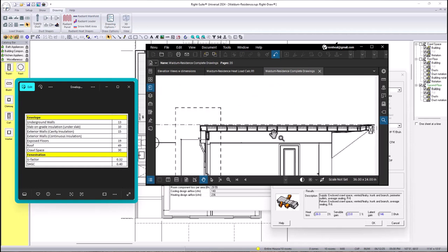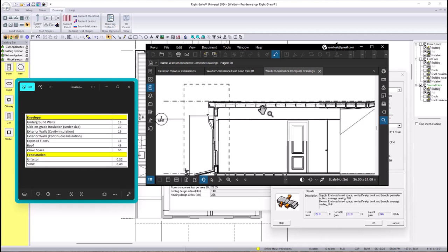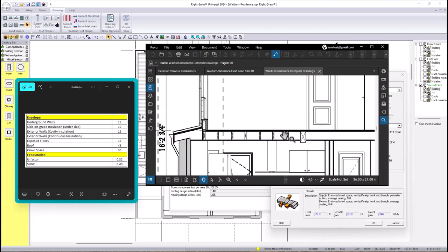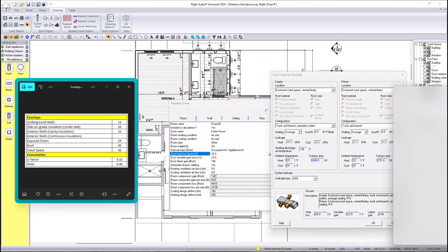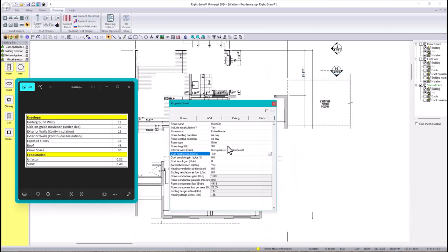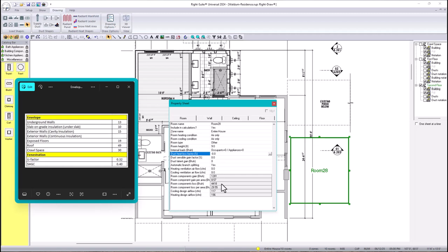Let's make this a little bit bigger. See, there's nothing, only insulation. But in here I have, so this requires coordination with the architect, but it's way better to run the ductwork in conditioned spaces. All right, so in that case, instead of supply and return, they're going to be conditioned, and then return is going to be conditioned, trunk, and then okay. See, as you can see, heat loss is 0, sensible, and latent is 0. So now we're good in here, we're all good.